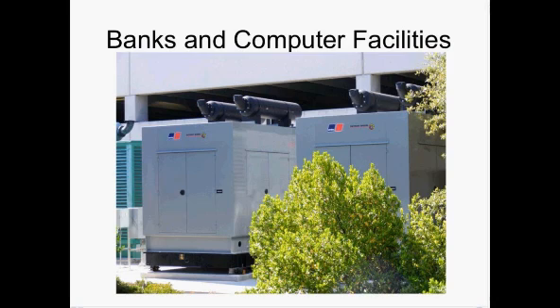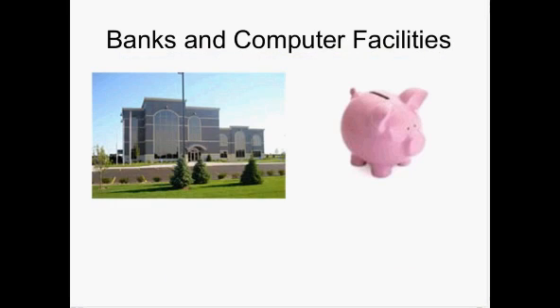Another important user of diesel engine generator sets is the financial institutions and data centers. Their computers and servers are backed up by UPS systems similar to the UPS system in the telecommunications industry. There is no interruption in the very important money transactions. This bank uses a relatively small diesel engine generator set to operate the computers and lights only. Only limited building management functions will have power on the emergency power system. One may only have to go without the air conditioners until the utility power is restored. What size generator set is installed is a business decision based on cost versus risk. The essential items will have power.